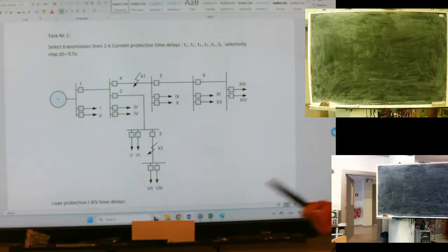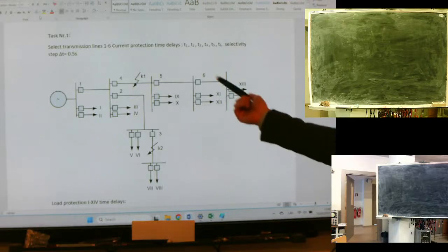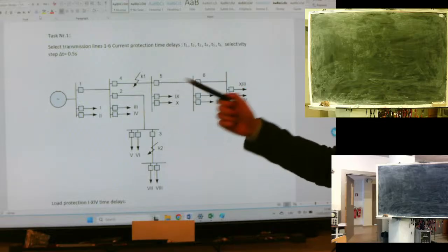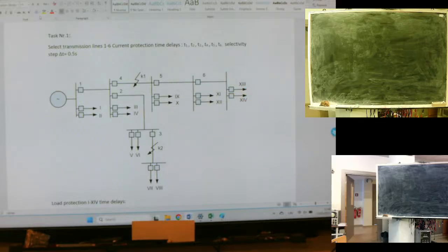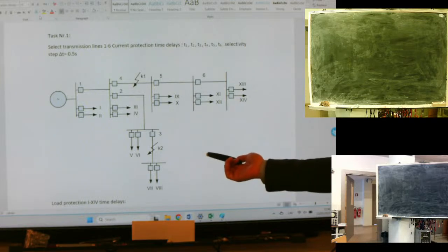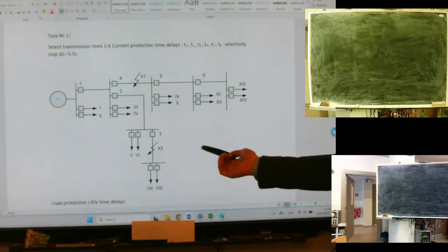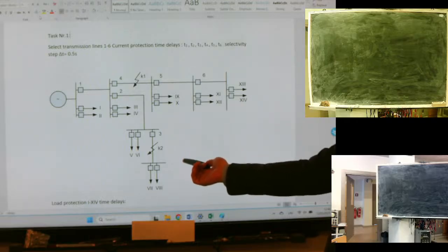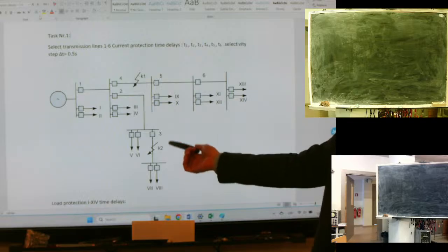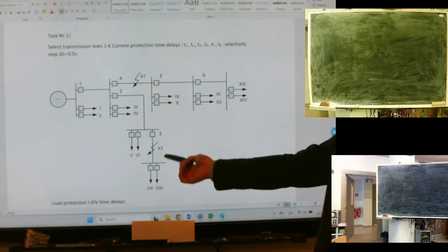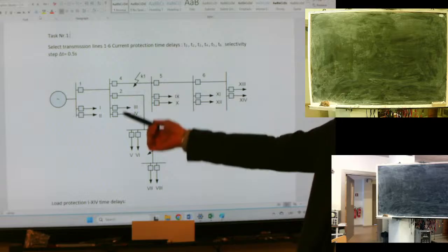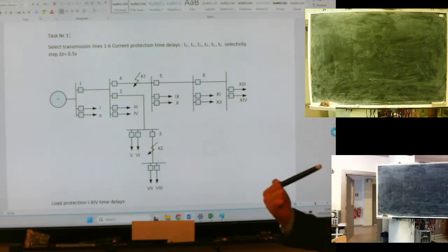We are protecting the load or we are protecting the network. If we are talking about line protection, we want to protect our network, our lines, from a fault. That means we need to isolate our network, our distribution, from the fault element. For example, this is line number 3, in this case. So we need to isolate our network from this element.